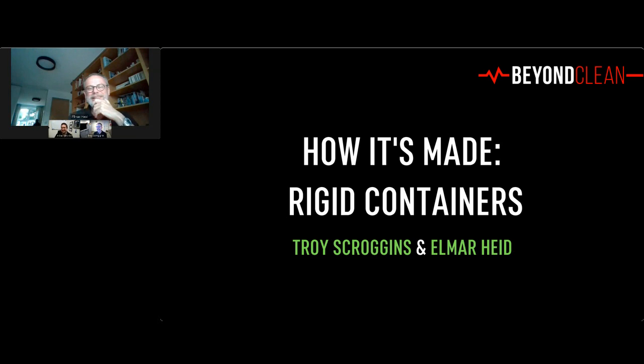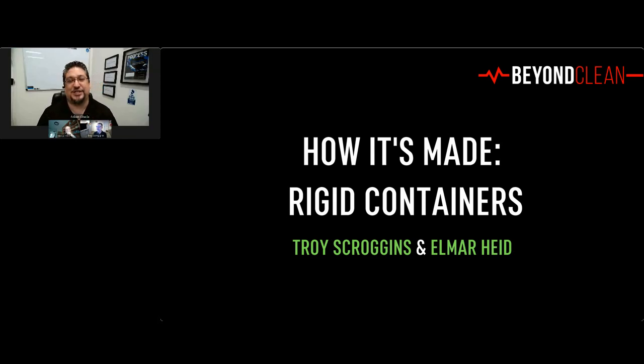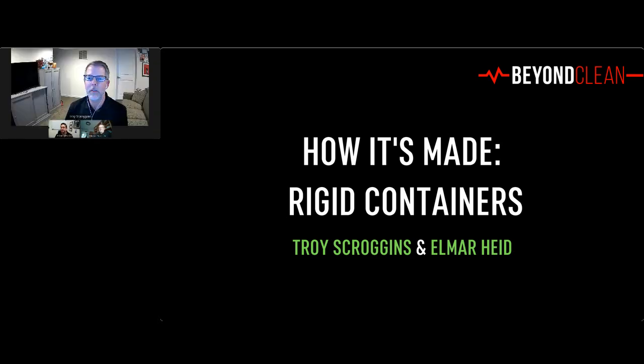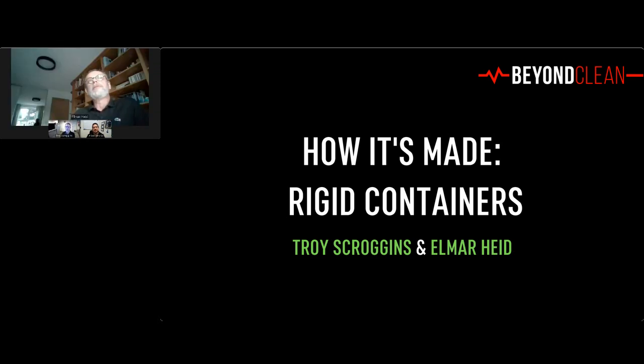Exactly, right. In the presentation, you talked a little bit about why aluminum is better than stainless steel because of the weight. But would containers made out of plastics possibly be another option? Is there a reason why aluminum is the best option out there? I'll let you take this one, Elmar. Yeah, thanks. From the point of view of a manufacturer, plastic materials would have some benefits, especially that they may be more impact resistant than an aluminum container. But on the other side, the big disadvantage of plastic materials, a little bit similar to stainless steel, is that they do not have a good drying property.